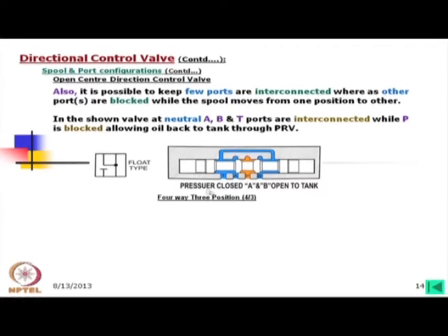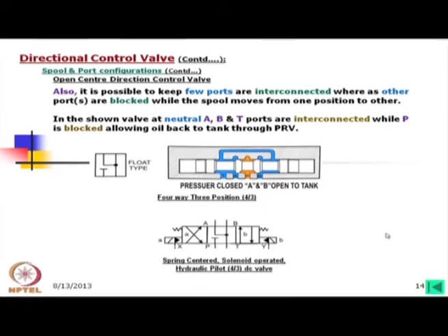say, the outer body is the completely closed center, the same outer body we can use, only the spool we have changed, we have reduced the thickness of the land at the two middle positions. Of course, it is not thin like what is used for open center. This means that on the same valve body we can use different spools to make different types of valves. Here the symbol is also the same; only in the driving part and the intermediate position there is a change.